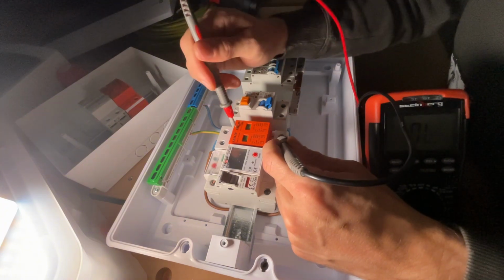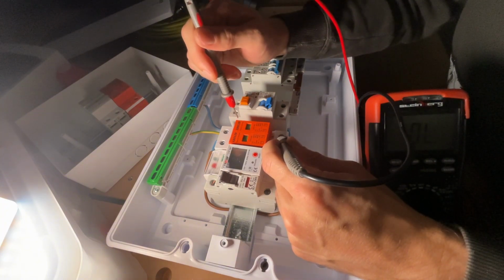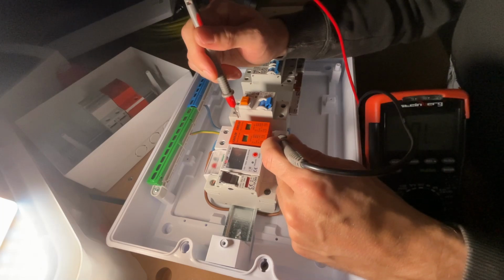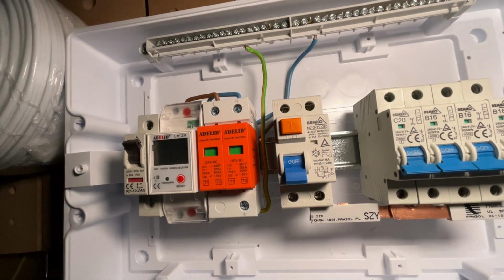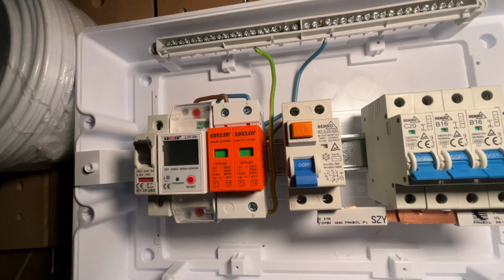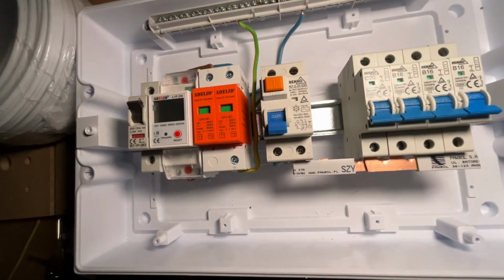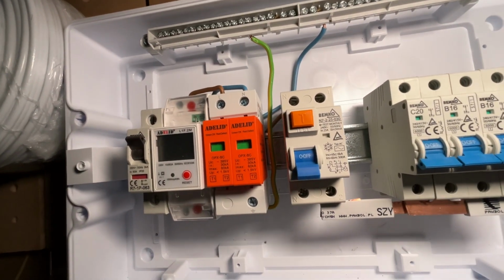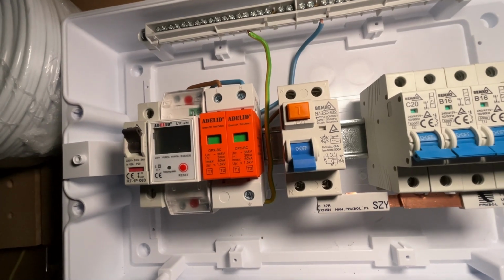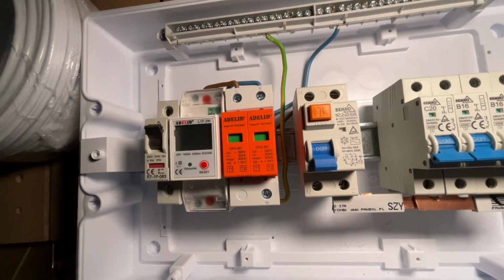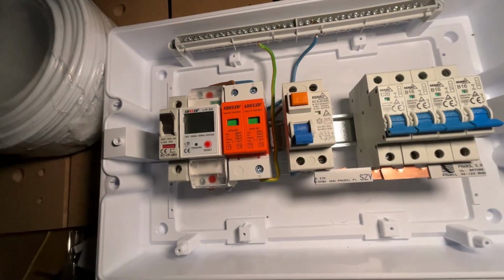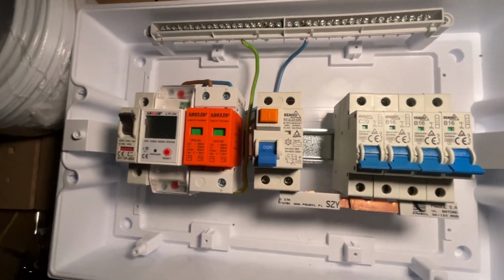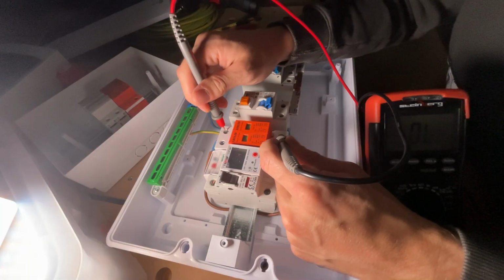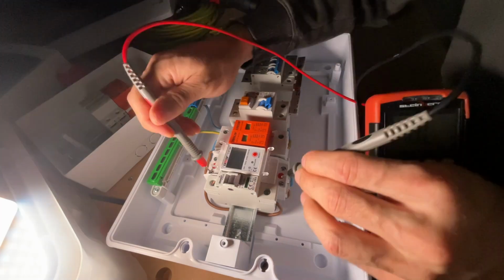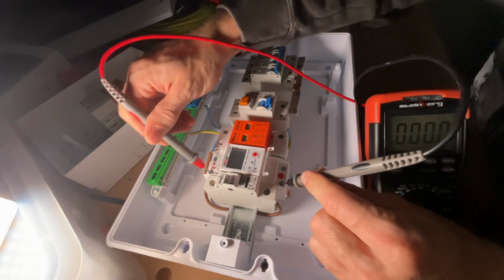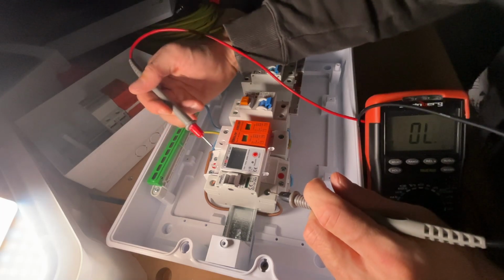Checked. Surge protection device, or simply SPD, protects your circuit from overwhelming voltage spikes, like when lightning strikes in the building or nearby, which may result in high voltage induced in your circuit. This device breaks and transfers all the energy to the ground. So, check. No beep. That's good. If there would be a closed circuit, that would mean that the SPD is broken or already used.